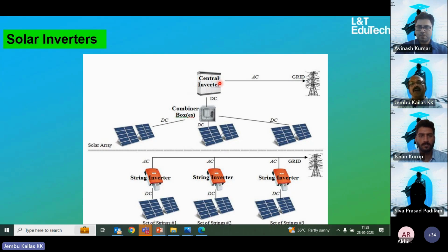This is also one of the requirements of the grid code from the government actually. If inverters, if the solar and renewables are going out from the grid due to any voltage dip, etc., then it will lead to disaster. Maybe this may affect the grid stability. As we are having more and more renewable energy systems on the grid, if the renewable energy is going out of the grid or going out of synchronism, then it will cause a lot of fluctuation in the system, and it will affect the grid stability. Okay, so one of the requirements is that it should always remain with the grid actually.